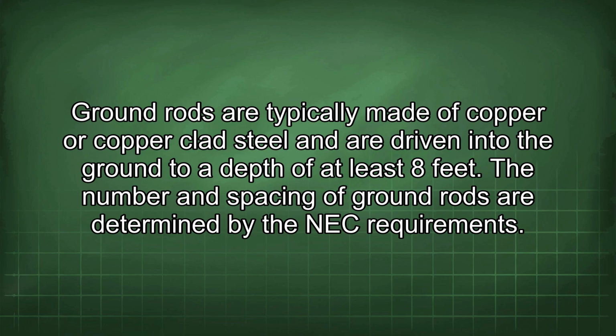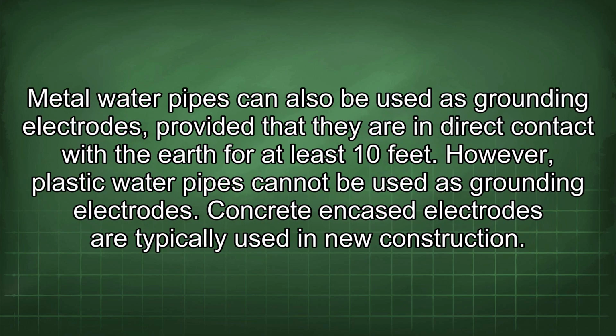The number and spacing of ground rods are determined by the NEC requirements. Metal water pipes can also be used as grounding electrodes, provided that they are in direct contact with the earth for at least 10 feet. However, plastic water pipes cannot be used as grounding electrodes.